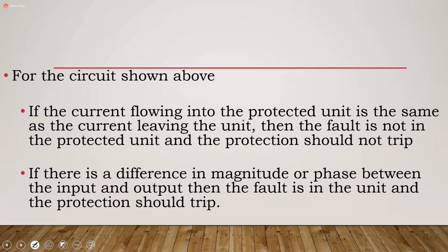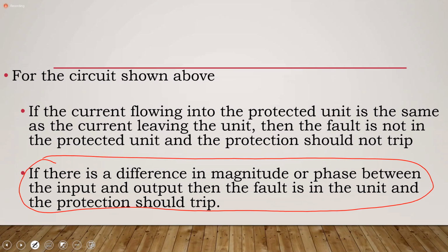So when you energize that transformer, part of the energy supplied to the transformer would be used just to energize the core. Why am I going through all of this? Because this point that we are making here, for your differential system, it would see a current going in, but it will not see the corresponding current leaving, because the current going in is being used to remagnetize the core before you see an output.